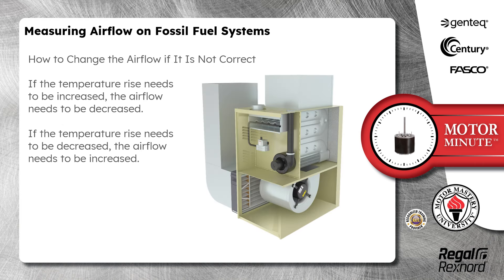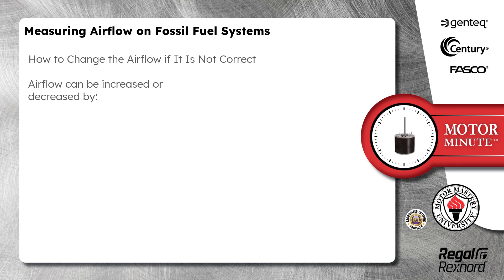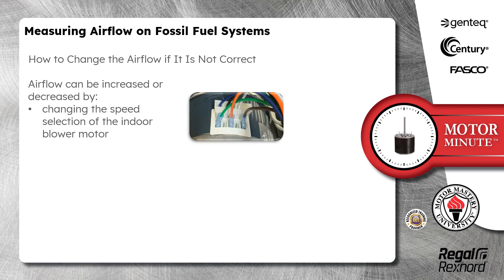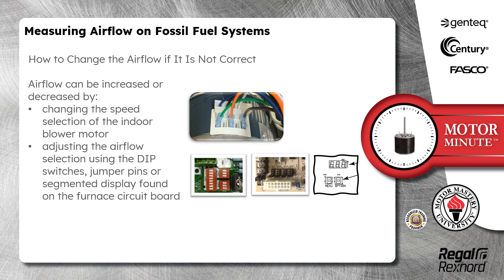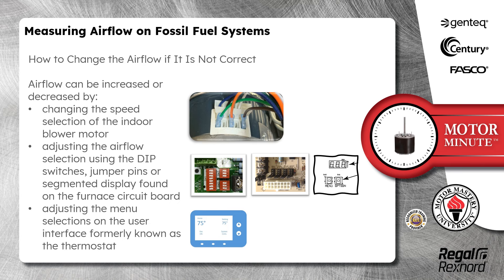If the temperature rise needs to be increased, the airflow needs to be decreased. If the temperature rise needs to be decreased, the airflow needs to be increased. Airflow can be increased or decreased by changing the speed selection of the indoor blower motor, adjusting the airflow selection using the dip switches, jumper pins, or segmented display found on the furnace circuit board, or adjusting the menu selections on the user interface, formerly known as the thermostat.